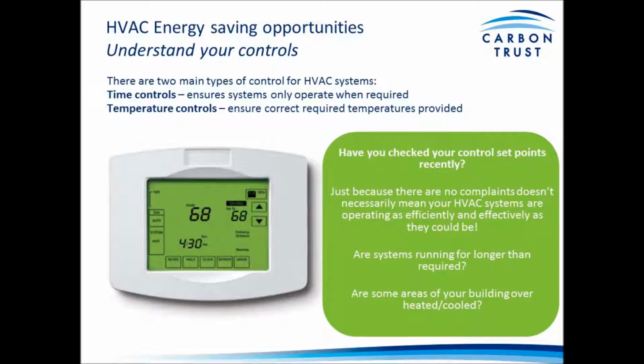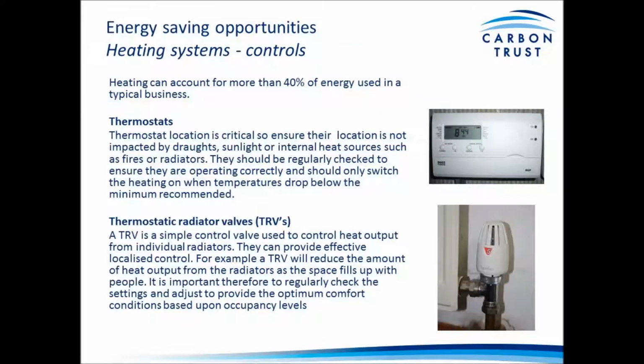And just because there are no complaints within the building doesn't mean that necessarily the controls are optimized. For an office building I'm working with currently, it is only by analyzing detailed metering data for the natural gas consumption that it became evident that heating systems are starting up around 3:30 a.m. every day, which is well in advance of when was needed to achieve optimal internal temperatures, and would have gone unnoticed because the building felt comfortable to occupants had that metering data not been analysed. So if you're not sure, check your startup and close down times, check your temperature set points, and make sure that the system is fully optimised. There are controls that can help do that and do these things automatically.